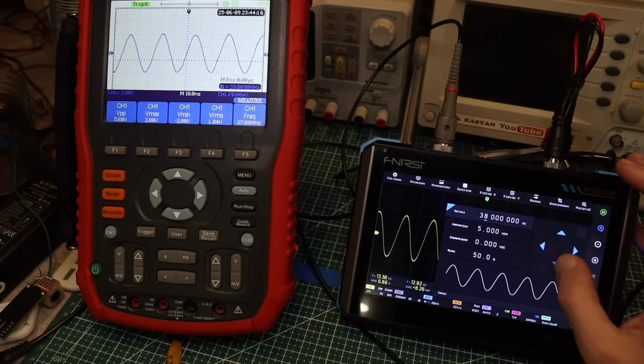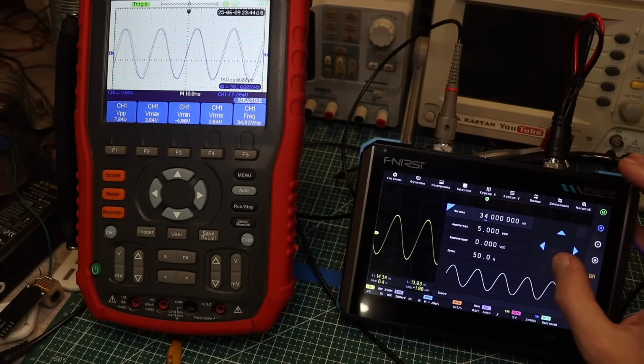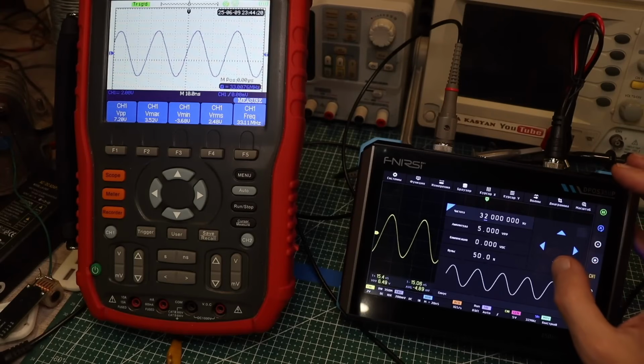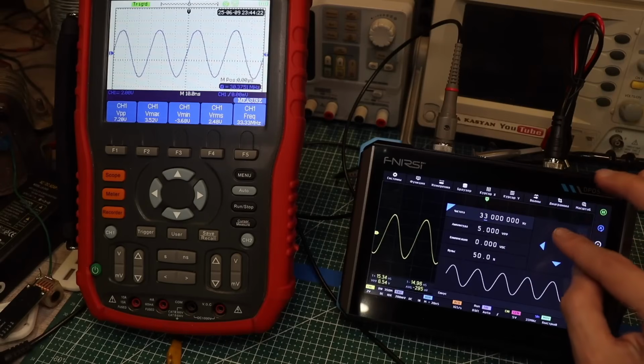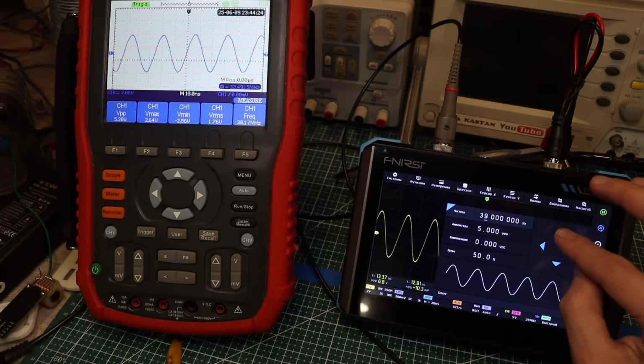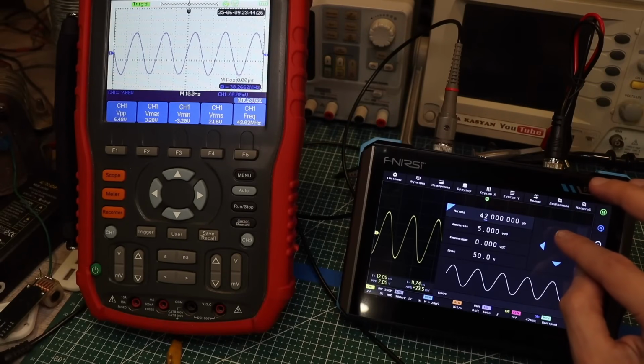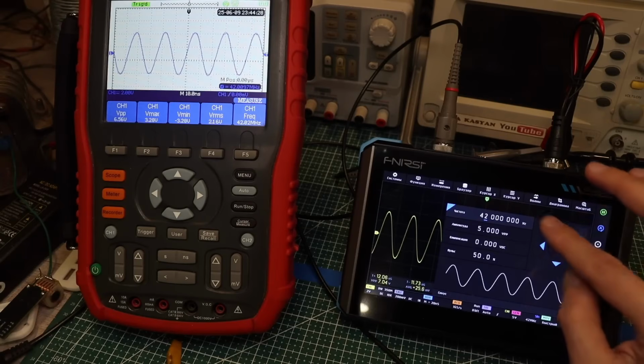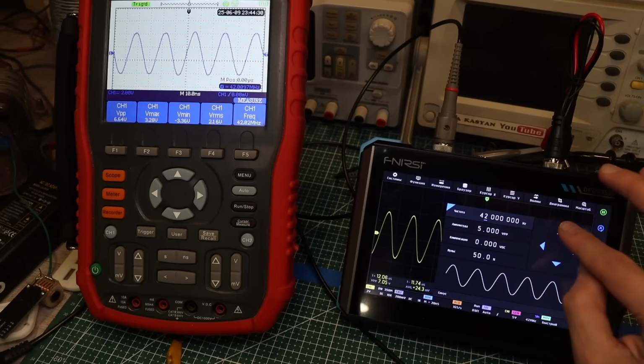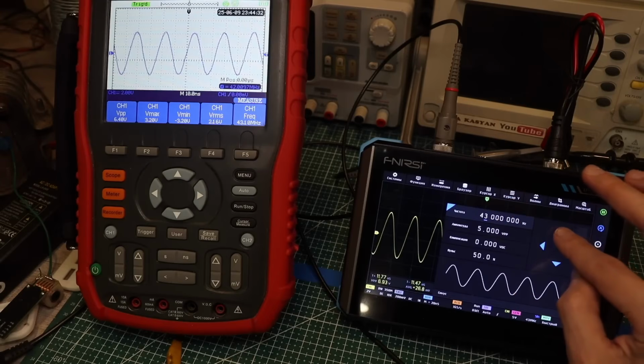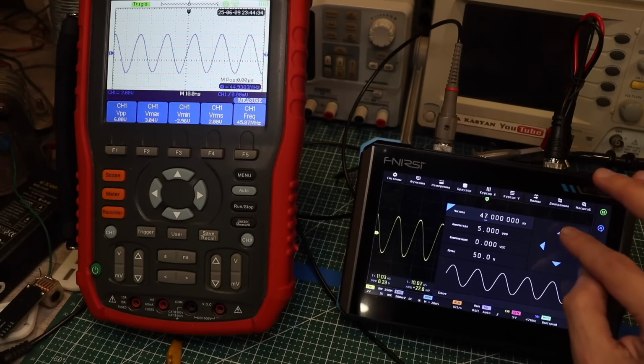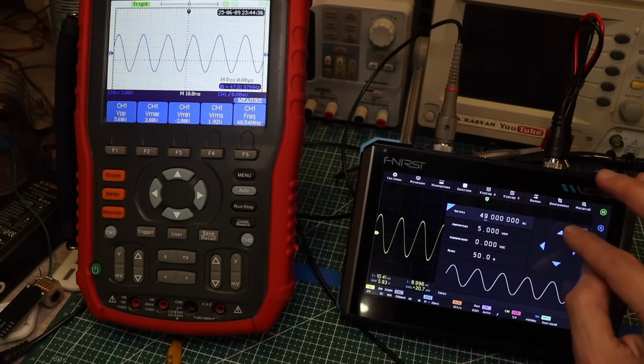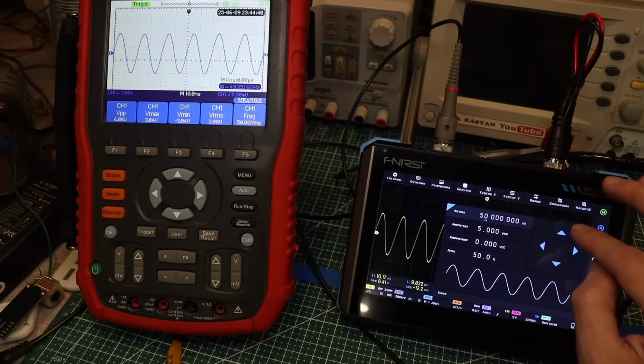We're seeing an overstatement. So there's this intermediate range where the amplitude is overstated, and then suddenly, there it is, 7.1 volts, and then it just starts to drop. So, if the frequency is above about 41 megahertz, it keeps dropping and dropping, and at 50 megahertz, interestingly, we still have 6.4 volts, so it's not a particularly serious drop.